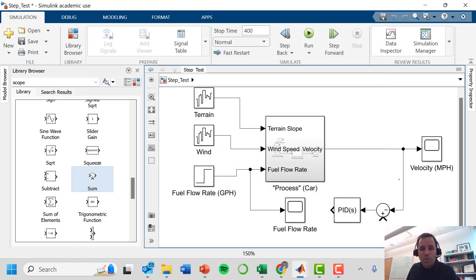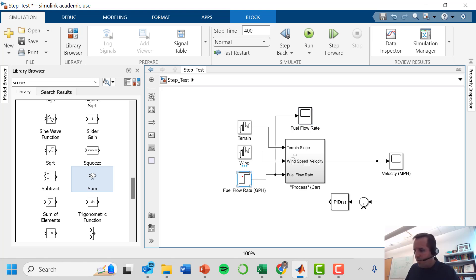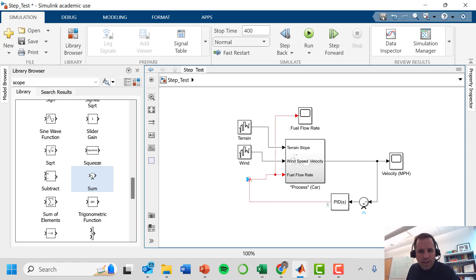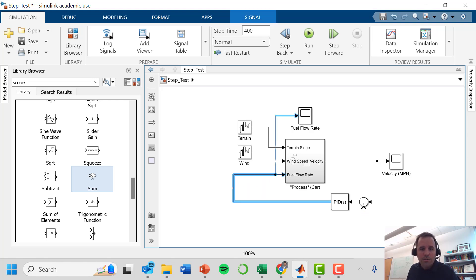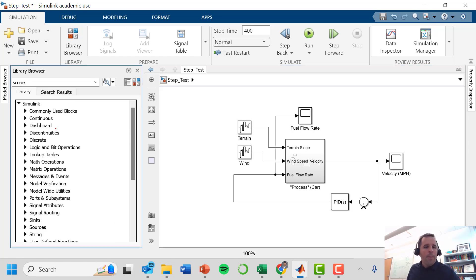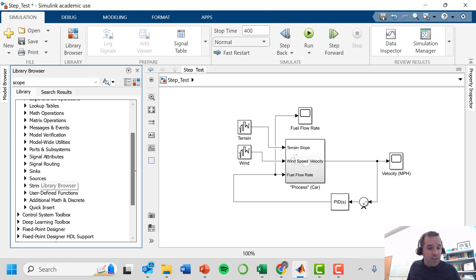The controller is now tuned and we're ready to run in closed loop. We remove the open loop step change for fuel flow rate and connect the PID controller output to close the loop. We need to provide a set point, and with proportional and integral control action in place, we'll test it by making an actual set point change to verify the controller keeps us at the desired velocity.